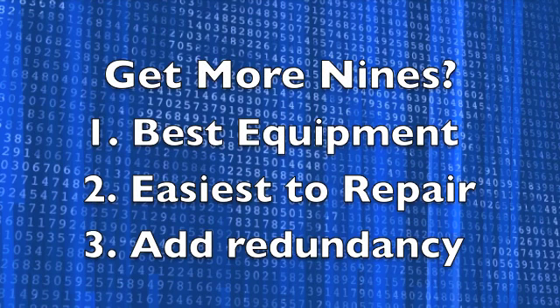How do you get more nines? Buy the best equipment that's the easiest to repair, and then add redundancy. Highly reliable systems often include multiple power supplies and processors, plus battery backup, diesel, or natural gas generators for longer power outages than batteries can handle. You'll also need multiple diverse communication lines, and extras of whatever else is likely to fail.